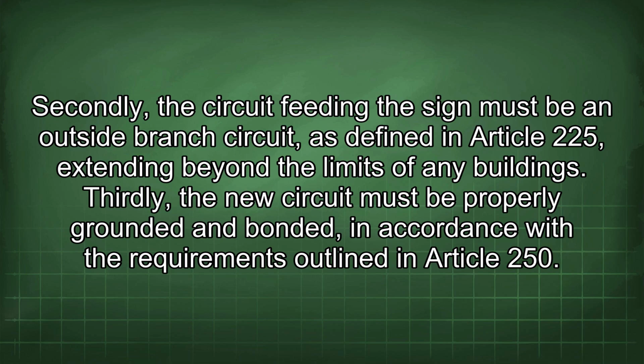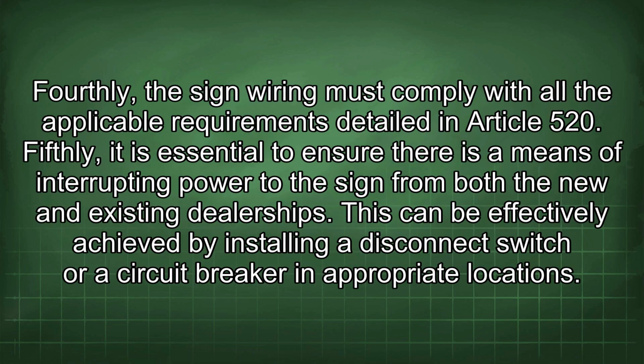in Article 250. Fourthly, the sign wiring must comply with all the applicable requirements detailed in Article 520. Fifthly, it is essential to ensure there is a means of interrupting power to the sign from both the new and existing dealerships. This can be effectively achieved by installing a disconnect switch or circuit breaker in appropriate locations.